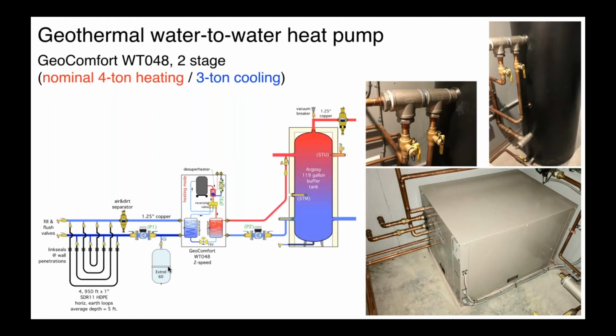And in the winter, what can happen is the piping will contract, but it contracts at a slightly faster rate than the fluid, and the pressure can get up to 50 or 60 psi, which in theory doesn't cause any problem. But you may have a joint that might leak or weep a little bit at 60 psi, and it wouldn't if it was at 15 or 20 psi. So putting an expansion tank in an earth loop stabilizes or reduces that pressure change. You're still going to see some pressure variation in the system, but putting an expansion tank in there reduces it. And again, if you want to read about that in detail, check out Hydronics number 9. We put the math in there to let you size those tanks up.